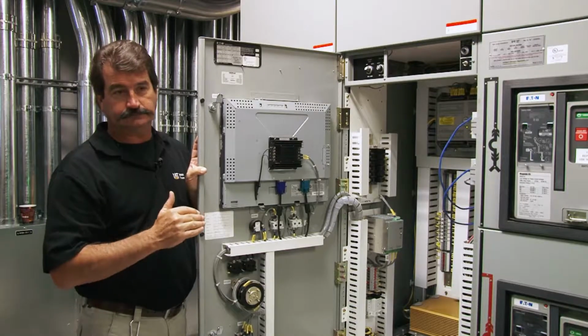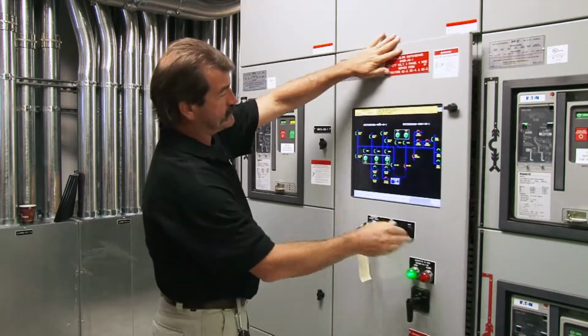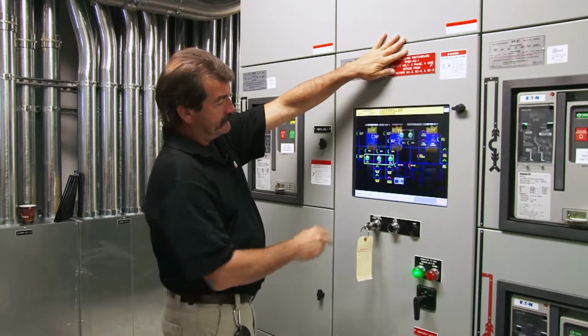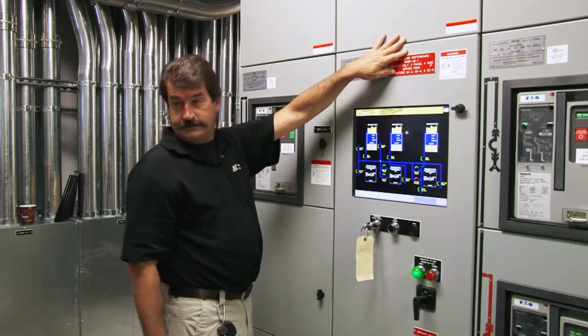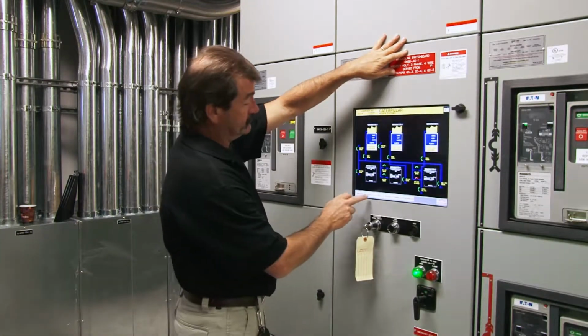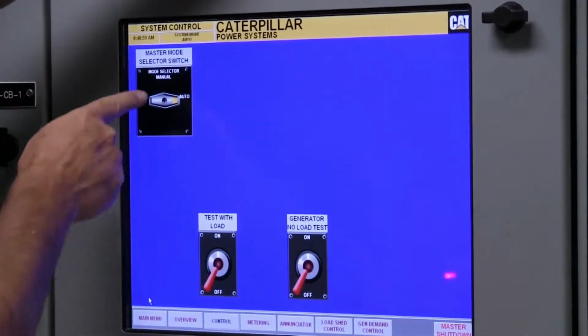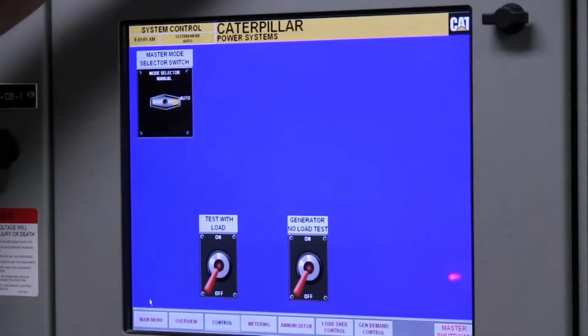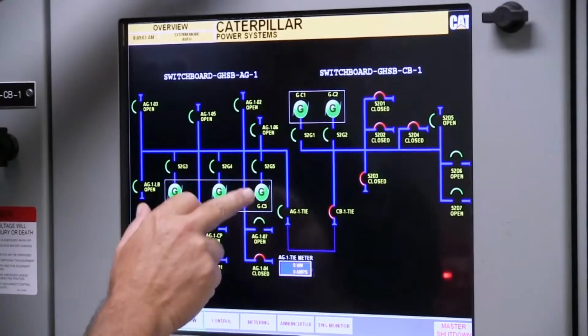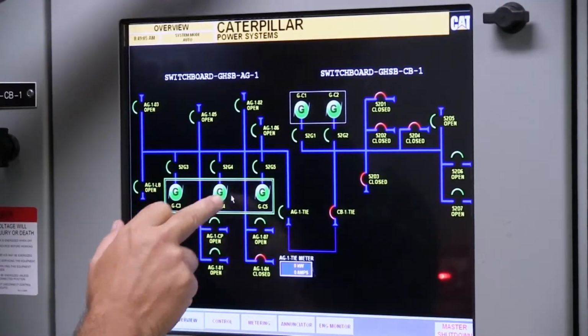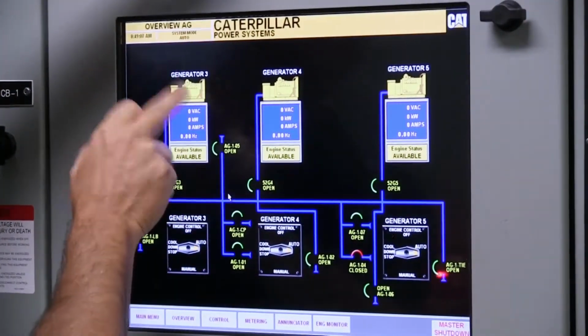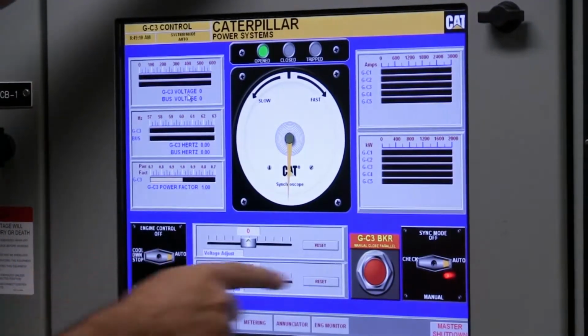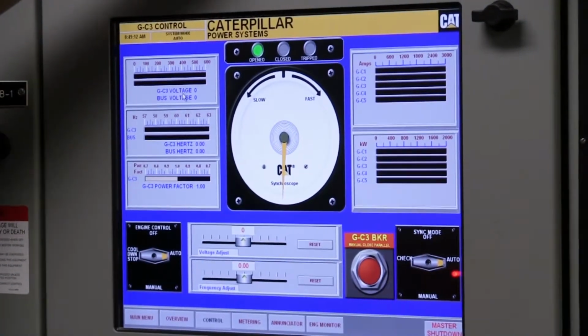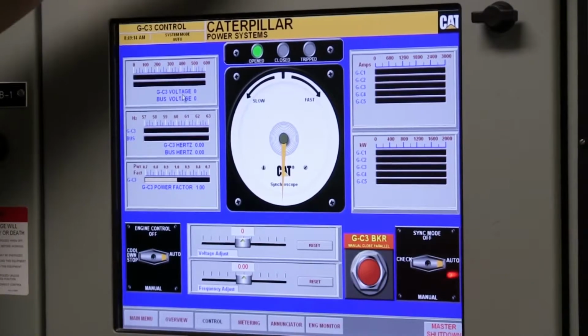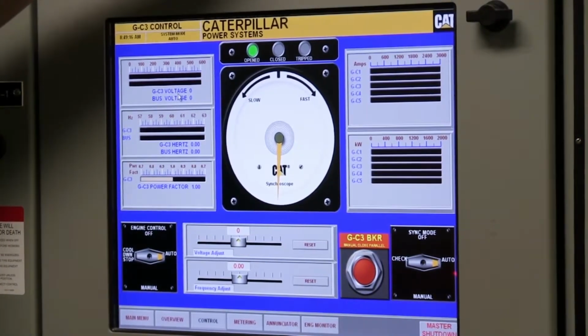That is an input into the controller that tells it to set every virtual switch we have back to Auto. Whenever I say every virtual switch, I mean your generator switch, your mode selector switch, your sync selector switches, and your switches for your circuit breakers. All those switches go back to Auto.